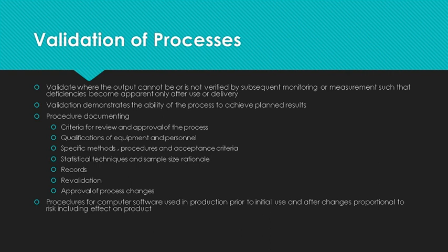The validation must demonstrate that the process parameter limits produce conforming product. Since this is ISO 13485, you need a validation procedure documenting the criteria for review and approval of the process, qualification of equipment and personnel, specific methods, procedures, and acceptance criteria, statistical techniques and sample size rationale, records, revalidation, and approval of process changes.